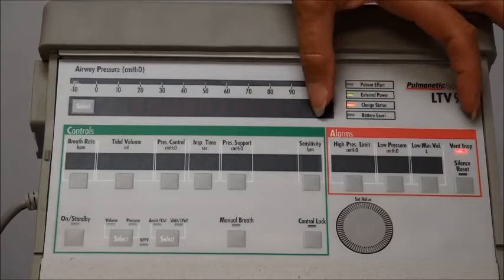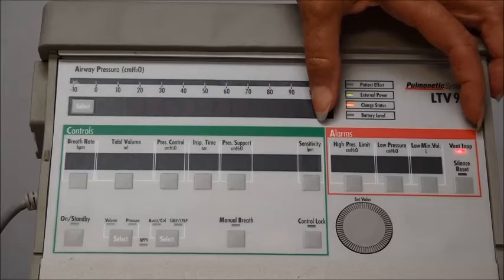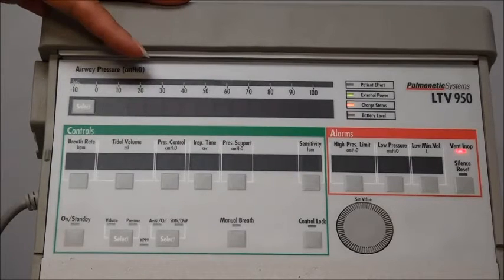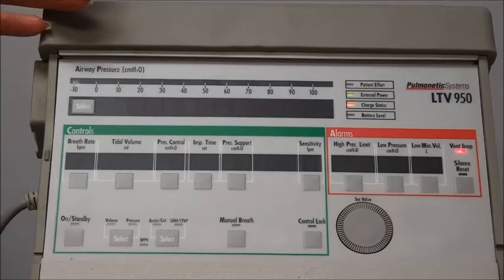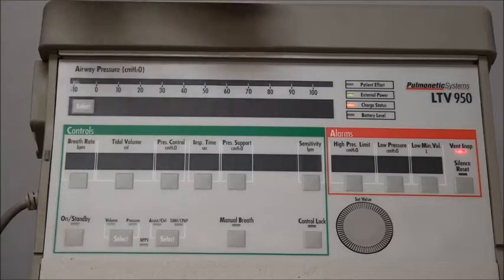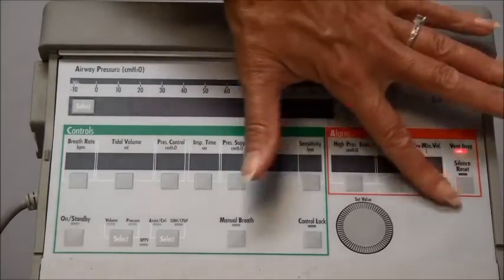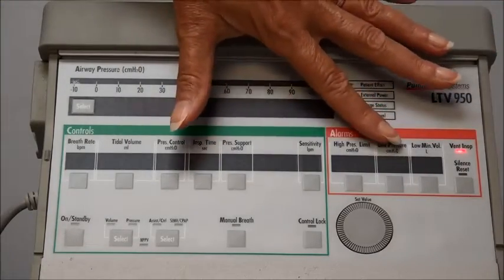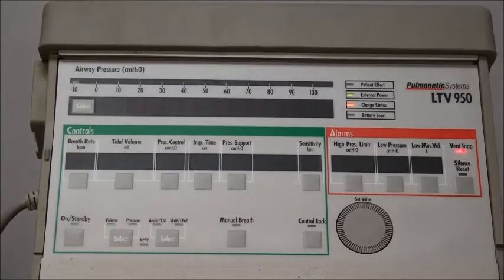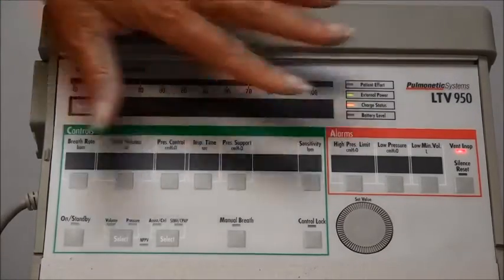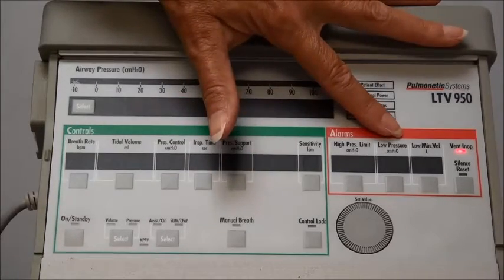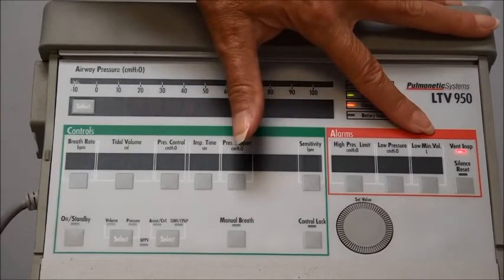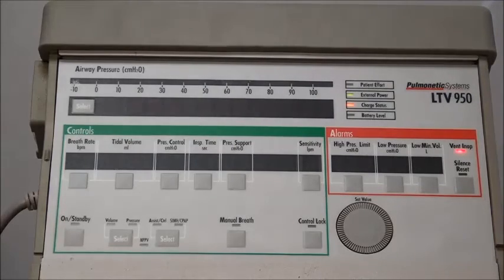Now, if we go over to the red box, this is where your alarm settings are. Now, there's other alarms that are set on this ventilator, but those are set in a different menu, and that's something that we would come in and set for you. You won't see those alarms, but these three alarms are what we'll set on the front of the ventilator, and you'll be able to see what they're set at. The first one is a high pressure alarm. The next one is a low pressure alarm, and then we have a low minute volume alarm, and I'm going to explain those to you in a moment.